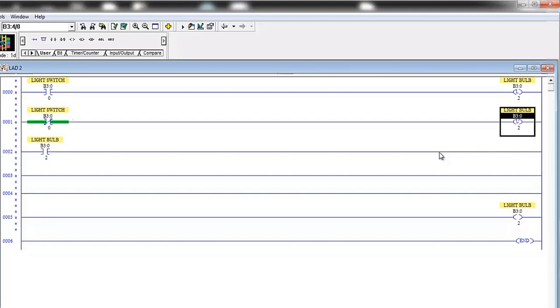And some of these conditions come and go in one scan. In other words, once a light bulb energizes, 6 milliseconds later, the conditions that caused it to energize don't exist anymore. So even if you track down all the places where you're energizing the light bulb, when you look, the conditions aren't met, so you can't even tell where in your program it got energized.